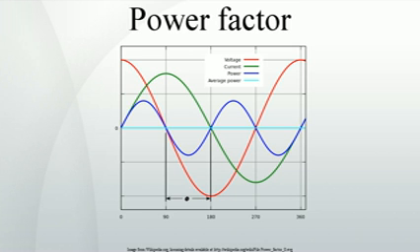Utilities typically charge additional costs to commercial customers who have a power factor below some limit, which is typically 0.9 to 0.95. Engineers are often interested in the power factor of a load as one of the factors that affect the efficiency of power transmission.